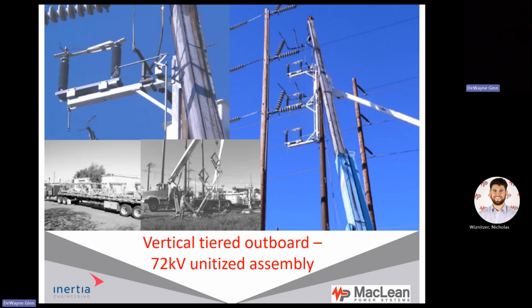This is a very unique one. This is a 72 kV that came in with a unitized backbone on it. This switch went up in 3 hours and was completely ready to go in 3 hours, which would normally take about 3 days to do. The downside is it has to come in on a flatbed truck because only one switch could come in on a truck at a time. You need a crane to lift it up, but installation is very quick and easy. There's a cost factor, obviously, with putting it on the pole, but it is a savings all the way around to the utility.